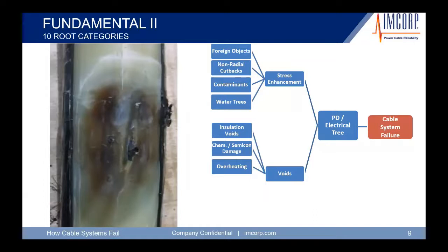The connector is very cable specific, and it has a die that's very connector specific, and it has a tool that's associated with those to put enough and the proper amount of pressure to make a connector. If it's loose, if it has sharp edges, these are areas where it can overheat the conductor or the insulation, breaking down that insulation, causing carbon tracks to eventually make this cable fail.